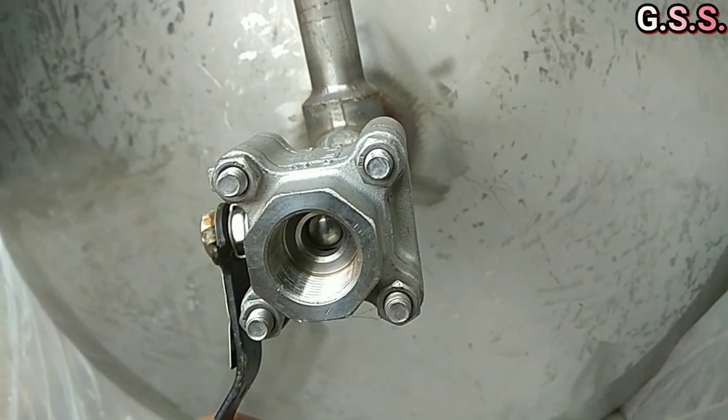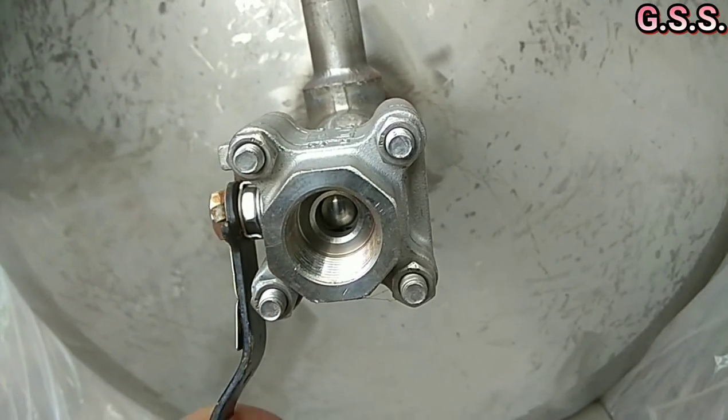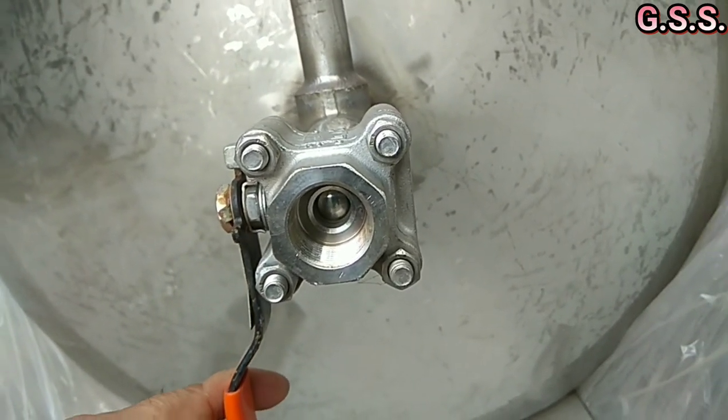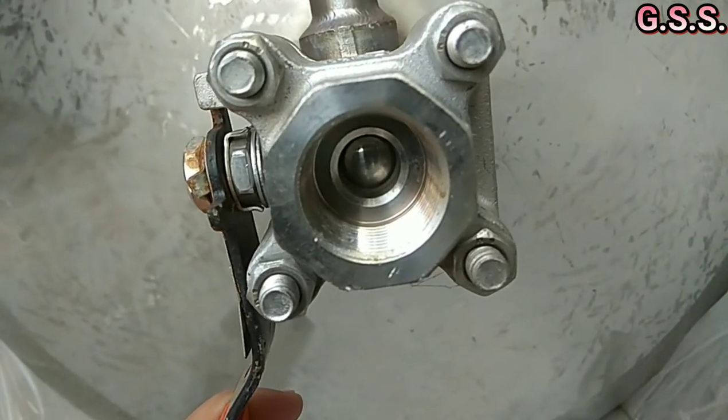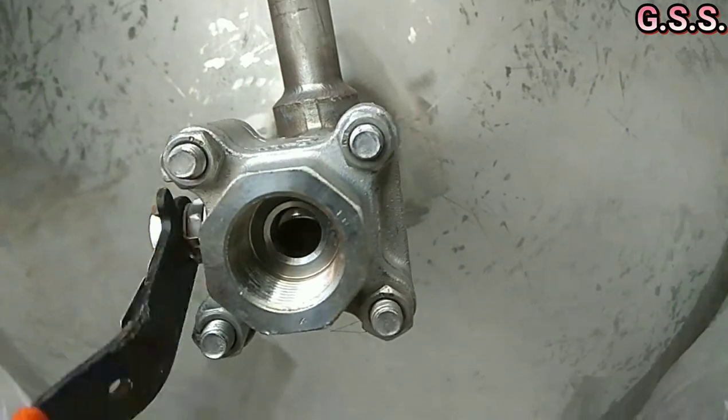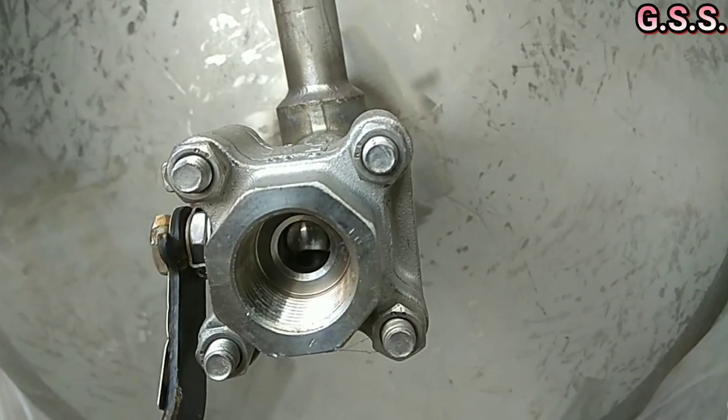Accumulated particles will rub the ball and eventually the reduced bore ball valve will not be leak-proof. So we should always use full bore ball valves, and during purchasing of ball valves, we should clearly specify this.